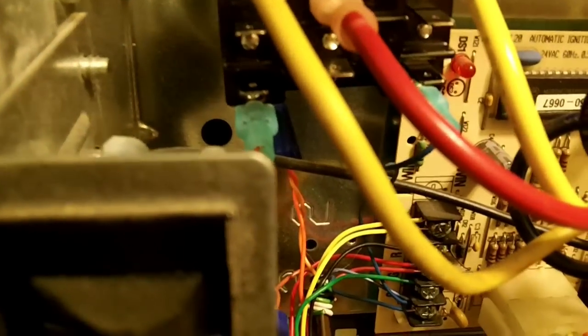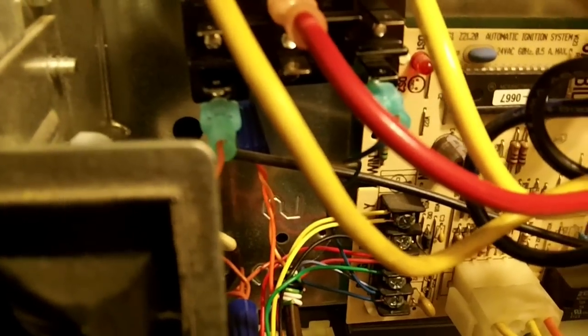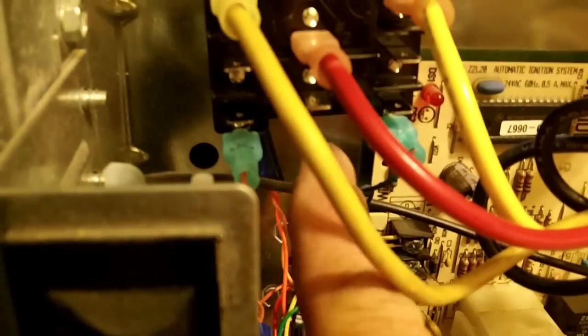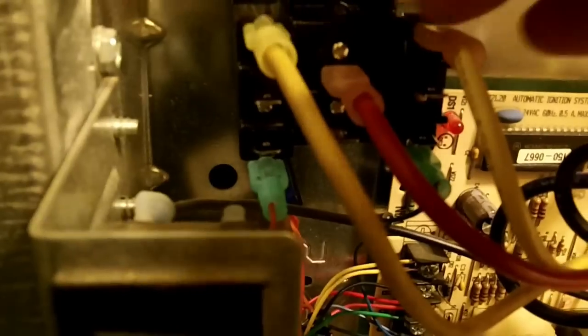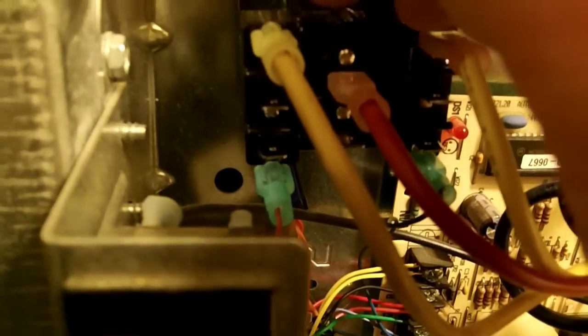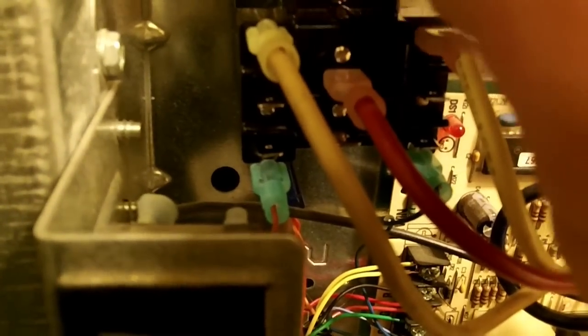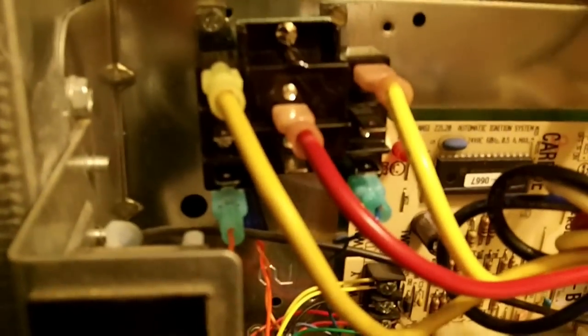Now when Y2 calls, it's going to go through the brown wire, send the signal to the relay—this is still powered because the G never lost power. So when the relay calls from second stage or Y2, it's going to energize the relay and send the power from here to here, turning the fan on at a higher speed.